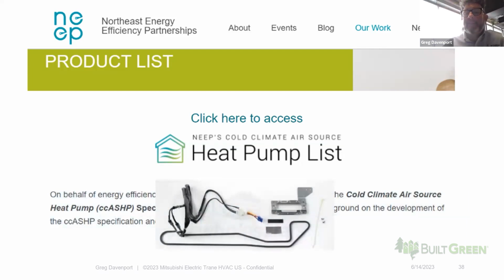This is what's called a base pan heater. If you're in a cold area, most likely your heat pump's going to need it. One thing that everybody needs to be aware of is the NEEP specification does not require that you put a base pan heater in your heat pumps. So if you put a cold climate heat pump in here that's on the NEEP list, but it doesn't have a base pan heater and it's really cold in the winter and your outdoor unit turns into a popsicle, you're going to have problems. The reason I say that is when people are looking for NEEP certified cold climate heat pumps, you really need to be aware of these nuances so you can design it right.